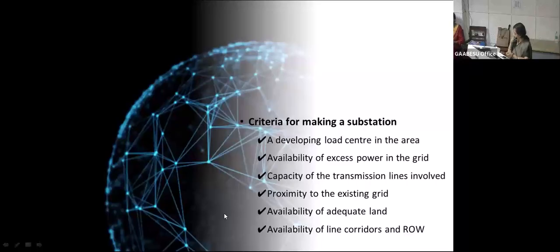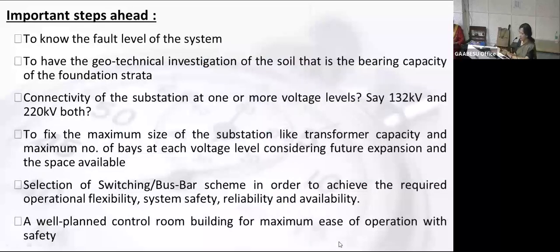So the connection to the substation from the available lines has to be looked at first, and also the line corridor and right of way for taking out the feeders. These are the physical challenges we face before building a substation. A lot of the time we do not get permission from the concerned government regarding land and regarding building a substation. So the challenges are always there for the industry.